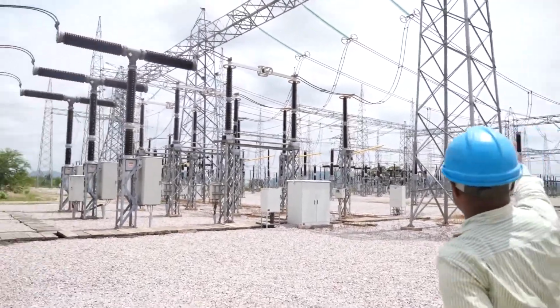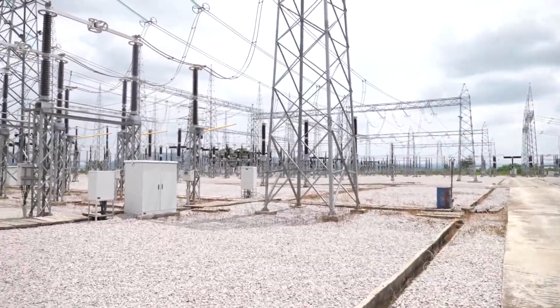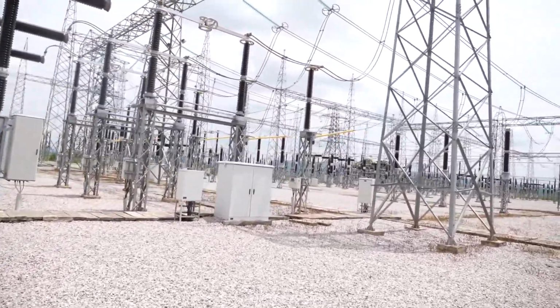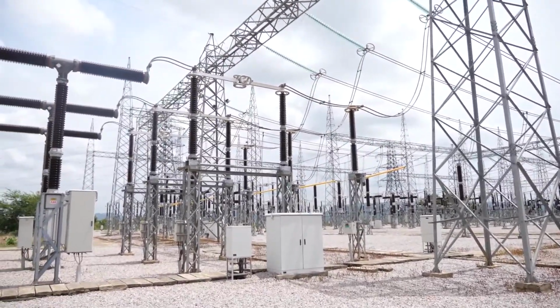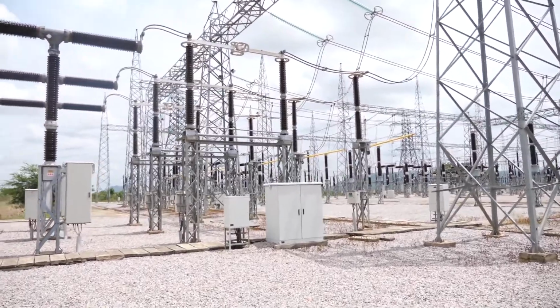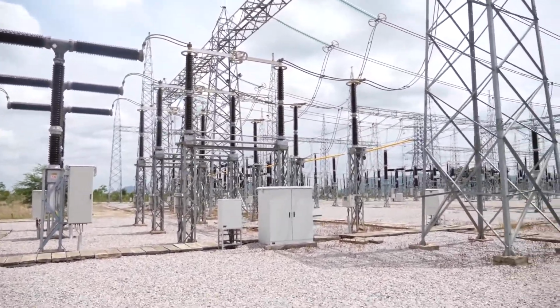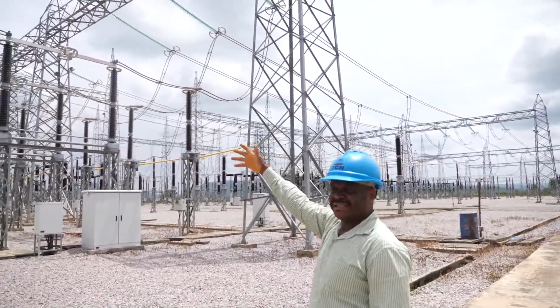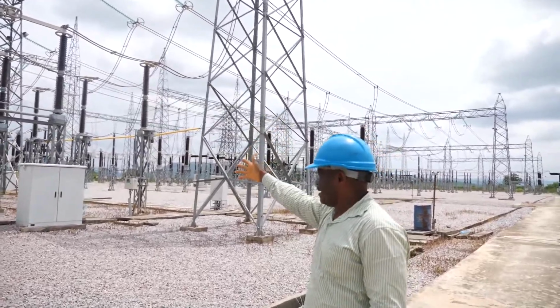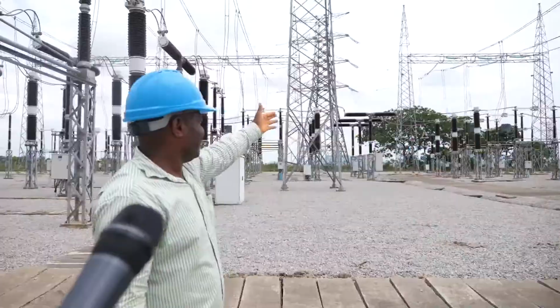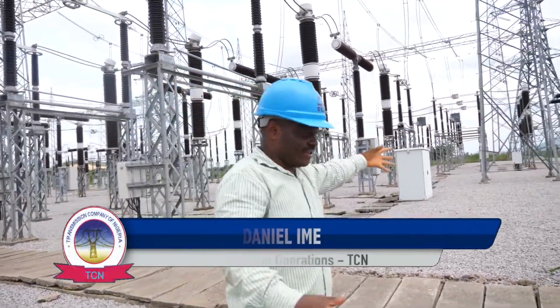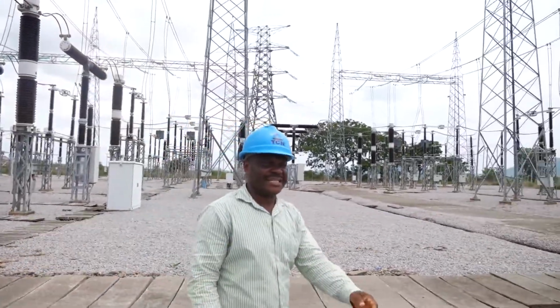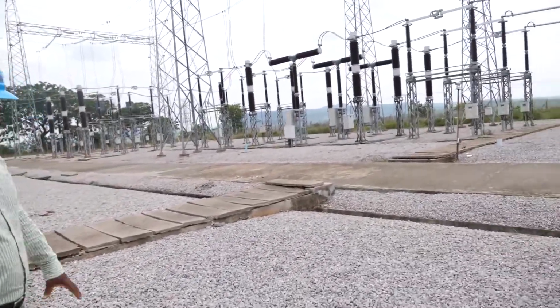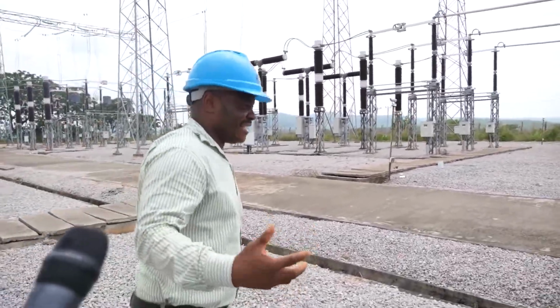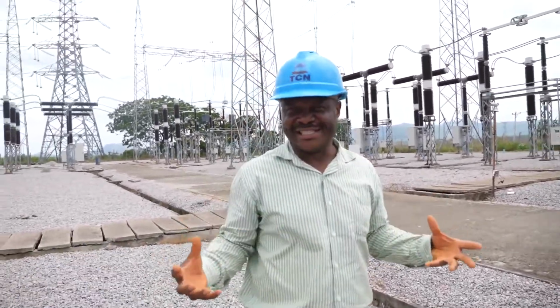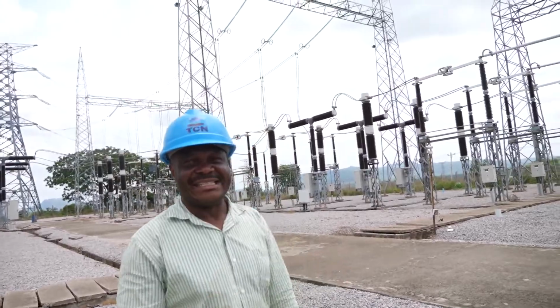So this is bus bar 1, the first one that you can see. And the other one down is bus 2. So there are 2 buses in the station. The source of the supply, like I said, we have 2 sources, 2 circuits, from Ajaokuta. So we have line 1 and line 2. They have the isolator, the breaker, and also the isolator. So with that, the 2 lines are tied together. The purpose of this arrangement is to stabilize the system, so that if there's any problem with one line, we will not lose the system. So that's one of the reasons that the tie arrangement is important.